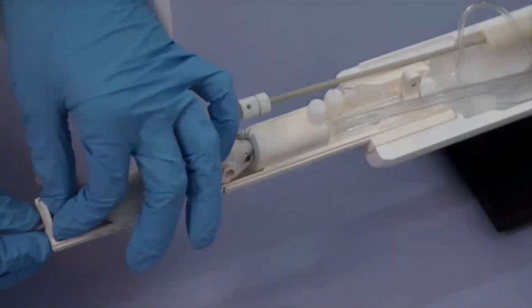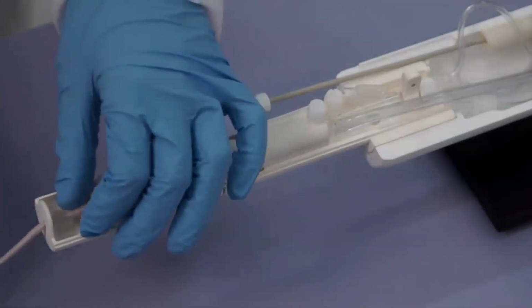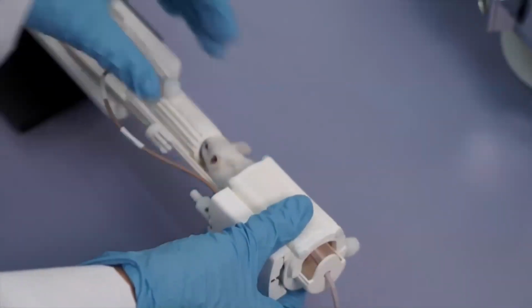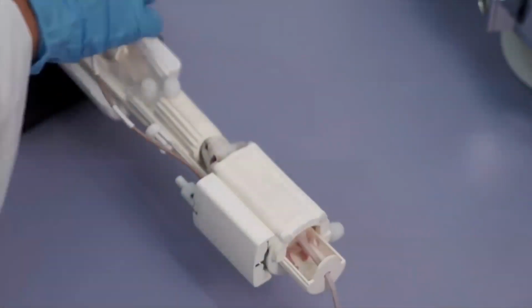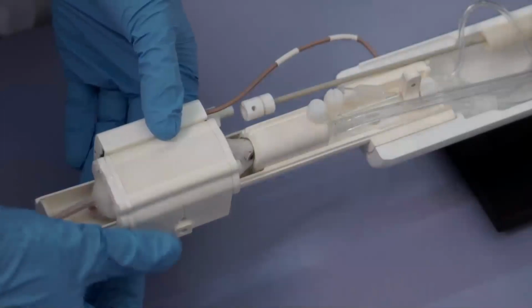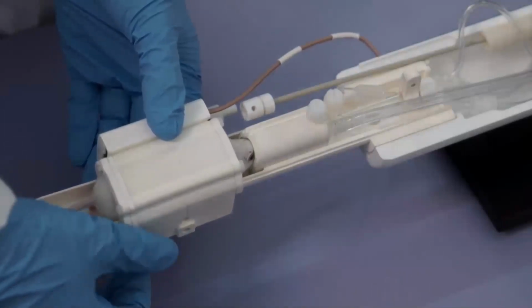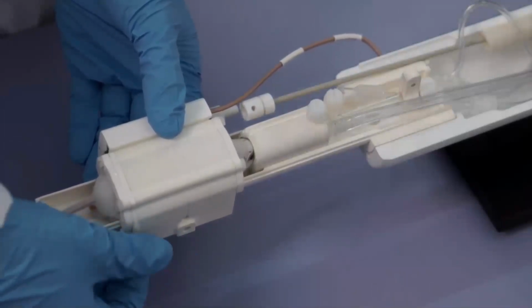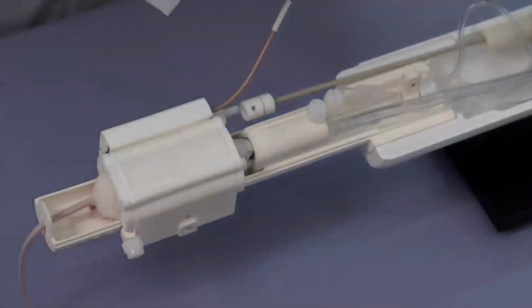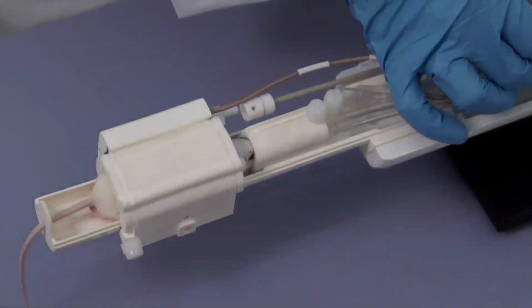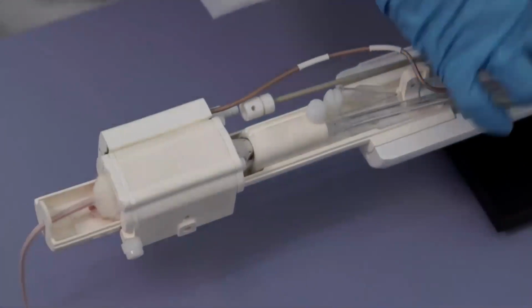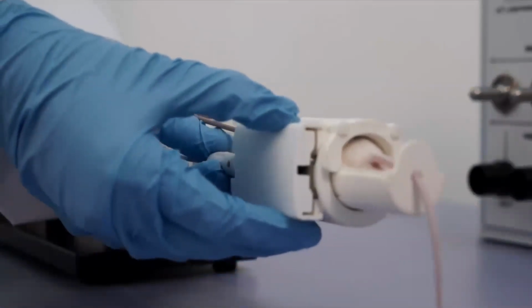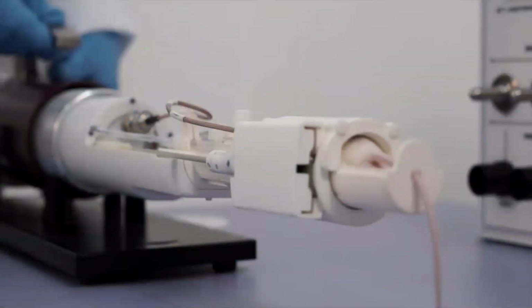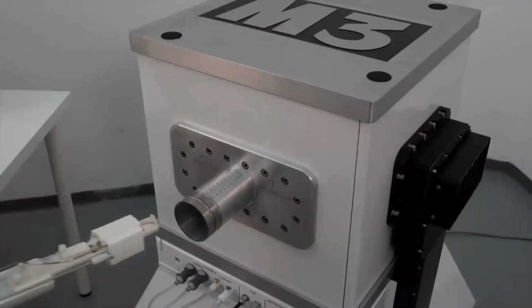The animal's positioned. If he's lower on the animal bed, the tail can fit through the little hole that was designed to hold the tail. The body coil would be slid over top of the animal. Again, if it was a head coil, that would be integrated into the nose cone. Position the anatomical target in the middle of that coil to give us the best image, and then join the electrical connection to the animal handling system, which again controls everything to the electronics cabinet.